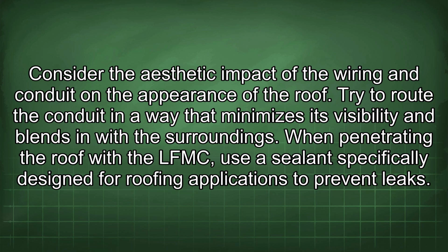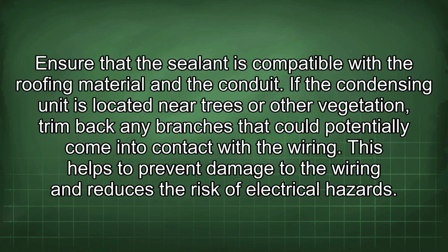When penetrating the roof with the LFMC, use a sealant specifically designed for roofing applications to prevent leaks. Ensure that the sealant is compatible with the roofing material and the conduit. If the condensing unit is located near trees or other vegetation, trim back any branches that could potentially come into contact with the wiring. This helps to prevent damage to the wiring and reduces the risk of electrical hazards.